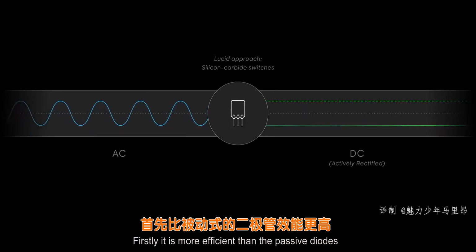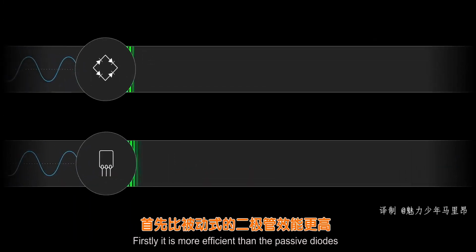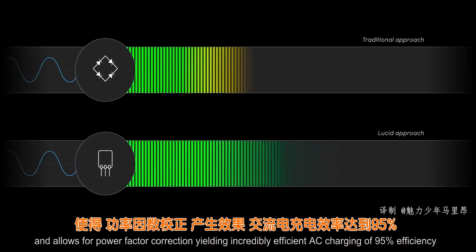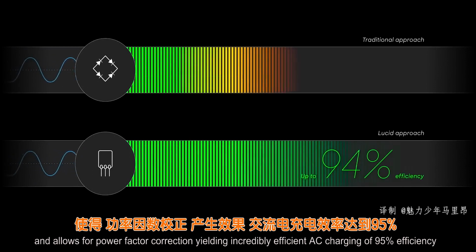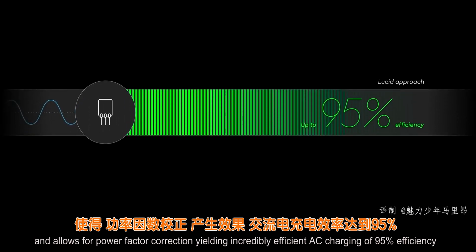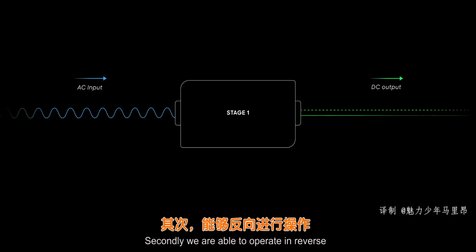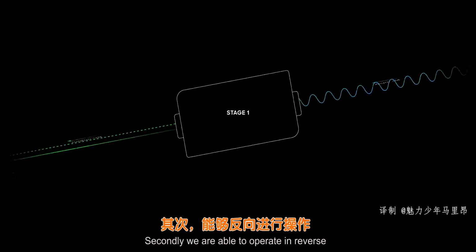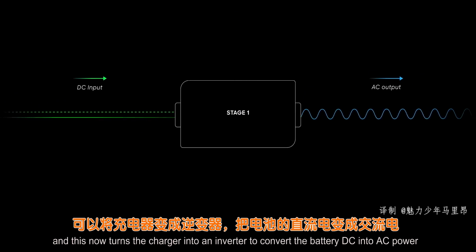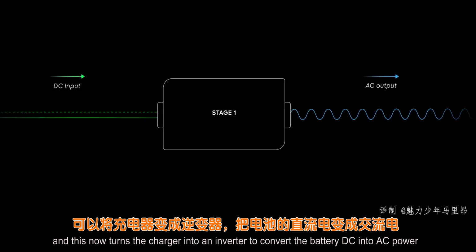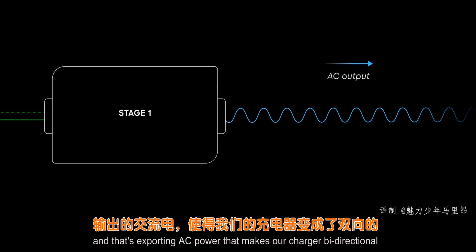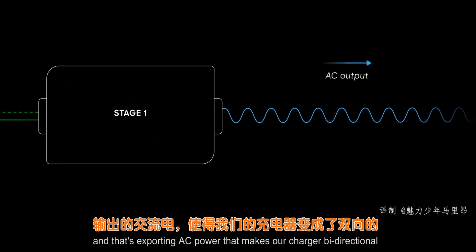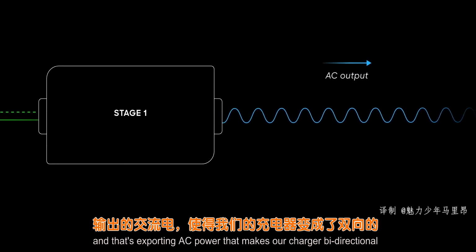Firstly, it is more efficient than the passive diodes and allows for power factor correction, yielding incredibly efficient AC charging of up to 95% efficiency. Secondly, we are able to operate in reverse, and this now turns the charger into an inverter to convert the battery DC into AC power. And that's exporting AC power that makes our charger bidirectional.